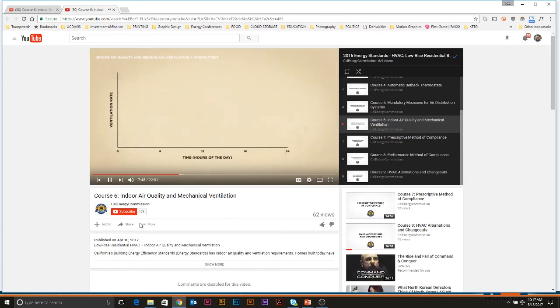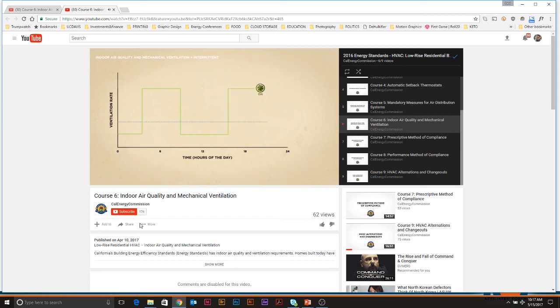The ventilation rate provided during the fan-on periods is higher using intermittent ventilation to account for the fewer overall hours of operation. Due to the decreased ventilating effectiveness associated with cycling, the total ventilation provided over a 24-hour period is higher than in continuous methods to maintain proper air quality during off cycles.